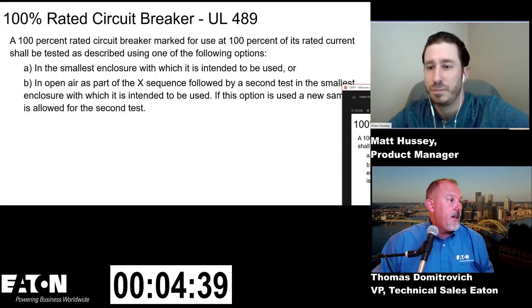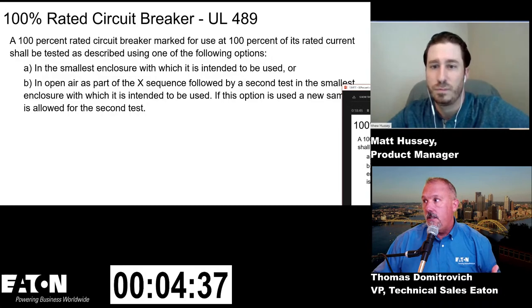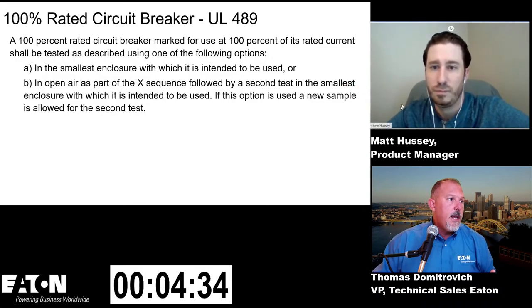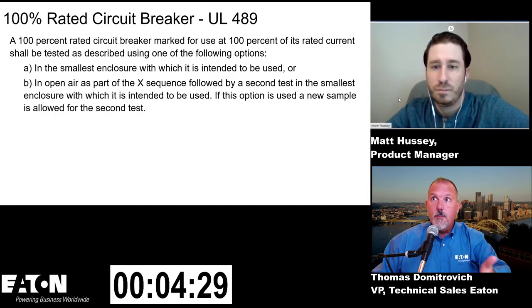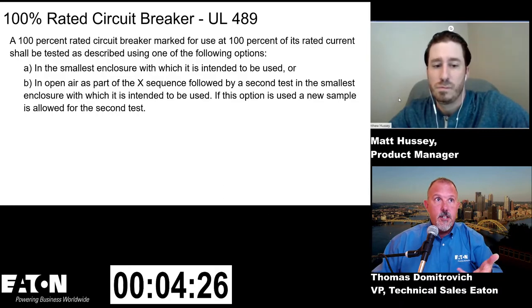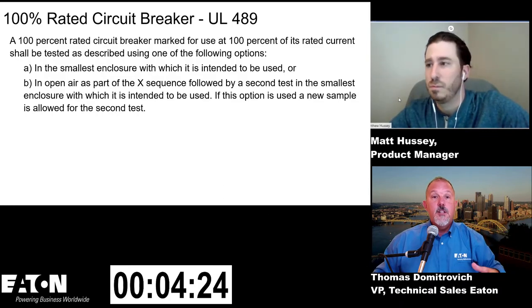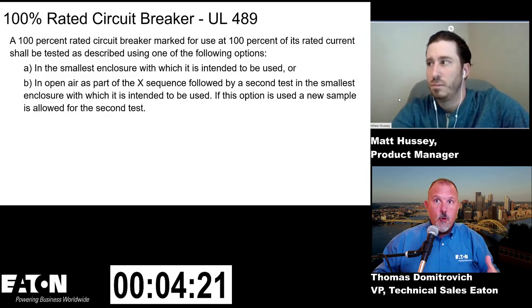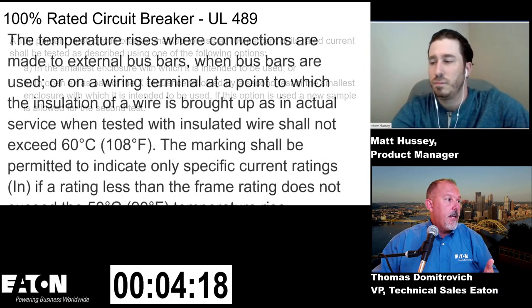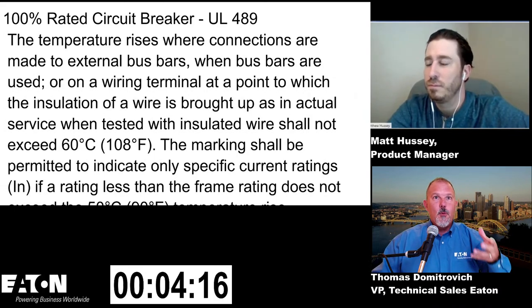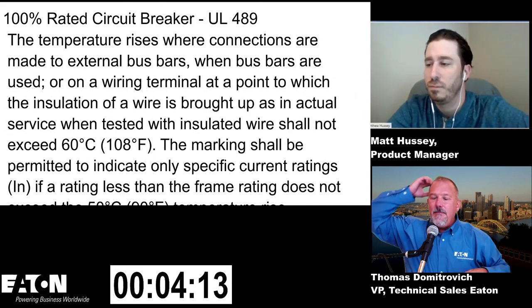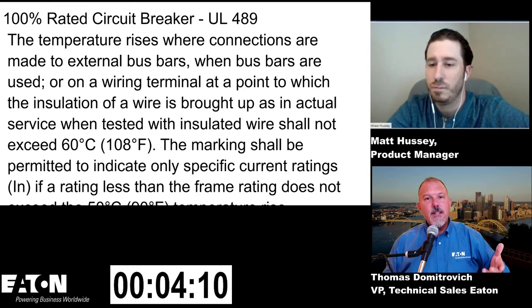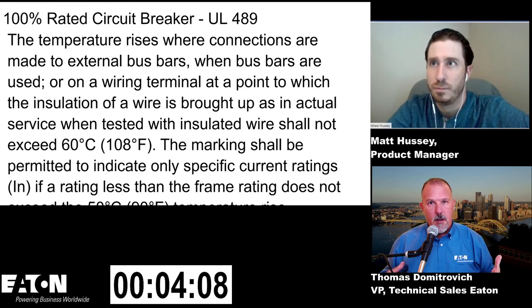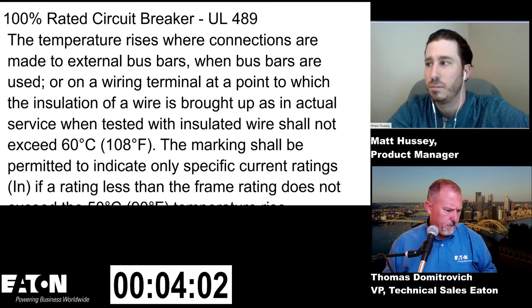Yeah, and UL 489 tells us that a 100% rated circuit breaker has to be marked as 100% and tested at 100% of its rated current, in the smallest enclosure and/or in open air, right? And the temperature, because we're always worried about temperature rise. And Matt, it's not the temperature rise in the enclosure that we're really worried about, right? It's the temperature rise on the lugs and on certain pieces of equipment, right?